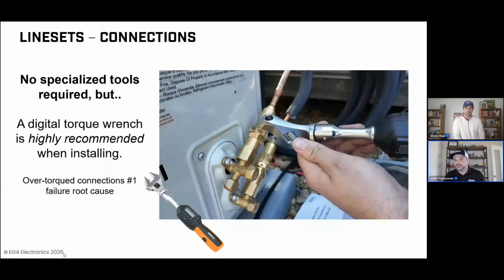Again, if you're not in the HVAC business, you might not have seen this before, but it's an open-ended adjustable torque wrench that you can use to connect the line sets. The torque spec represented in the manual is between 19 and 22 foot-pounds on those brass fittings. Over-torquing beyond the 22 foot-pound spec will cause cracking, so always be careful of that because they are brass connections. And then obviously under-tightening, or not torquing to spec, would cause a refrigerant leak. So this is one area that we always encourage people to be a little bit more sensitive with, and make sure that you have the correct tool to do the job here.